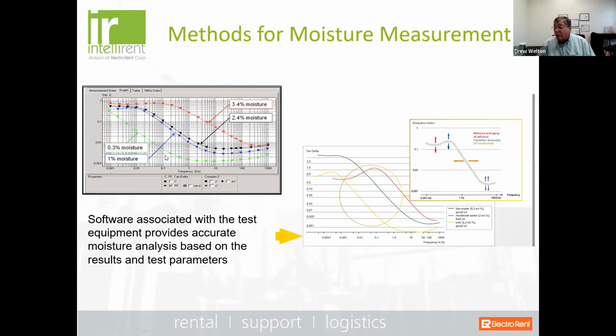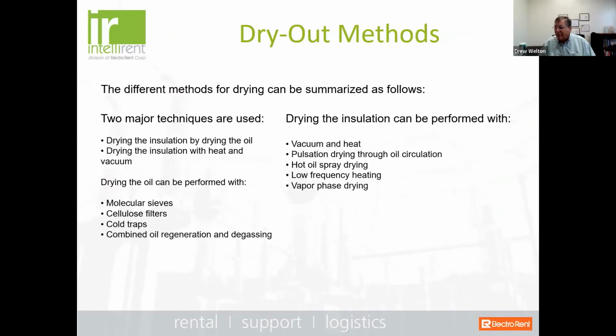And you'll see the characteristic of the curves of the measurements at the very wide frequency range here. And you can see that the higher your influence is here, the higher the moisture content. The good news is that the software that comes with these devices actually does this calculation for you, and it will tell you. But again, very important because it is a temperature sensitive measurement to actually apply those measurements into the test parameters before you get your results.